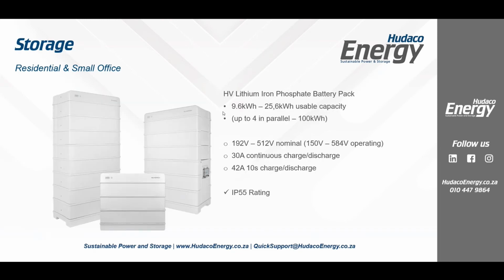Storage side, it's a high voltage lithium iron phosphate. This is a 9.6 kilowatt hour unit. You can see there's 3 batteries here. This is the largest single battery that we can run on the single phase unit, 1, 2, 3, 4, 5, 6, which is 19.2 kilowatt hours. This is 9.6 kilowatt hours usable. We could put up to 4 in parallel.